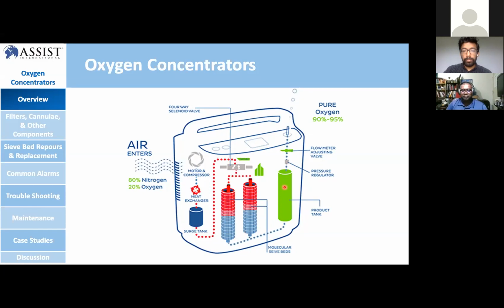The product tank is mainly there to make sure the flow of oxygen stays stable, because the sieve tank will keep on switching. During that period of time, you may lose pressure, so the product tank keeps the pressure at the same level, so there's no loss of pressure. From there, it goes to the pressure regulator and flow meter adjustment valve. Then you get pure oxygen of 90 to 95%. So that's how an oxygen concentrator works.